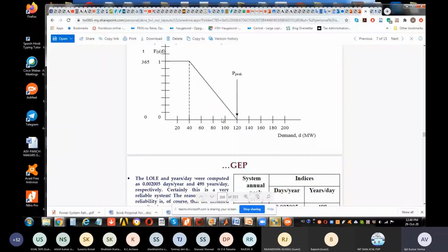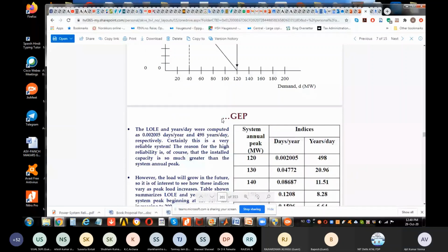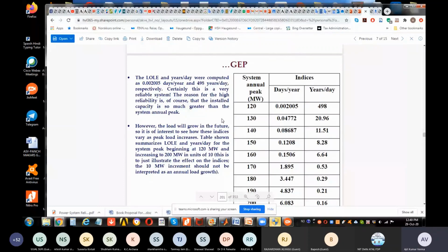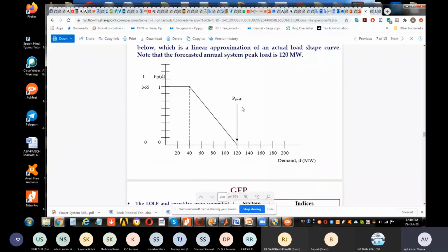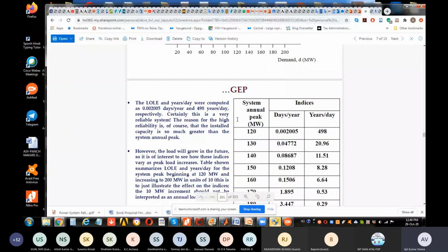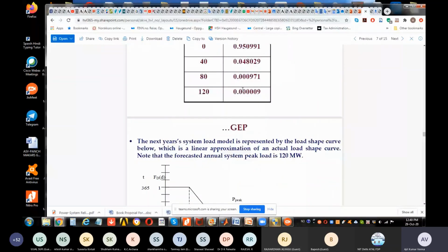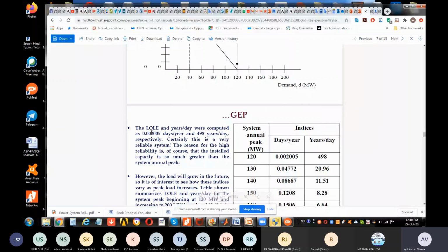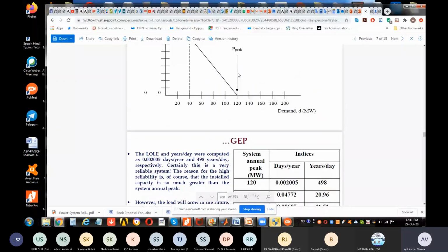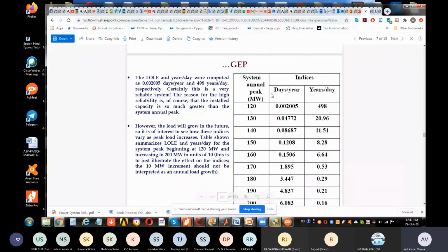So first we calculate the indices, and then we decide about planning and so on. These are the peak loads. Here the peak load is not beyond 120, but you can calculate with the generation profile and the load profile what the LOLE would be. So the LOLE was calculated to be 0.002005 days per year. That means in 498 years there would be one day of loss. This is the peak load of 120, and now we need to calculate the LOLE.